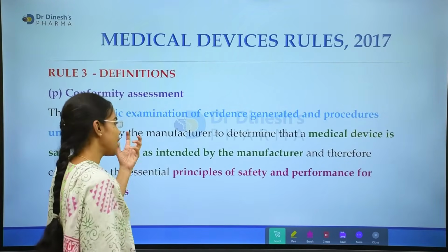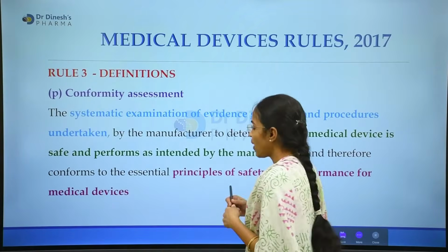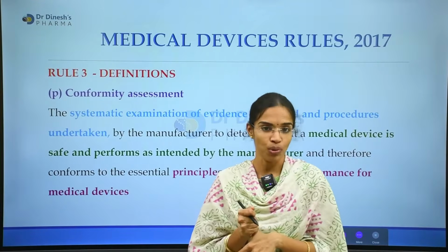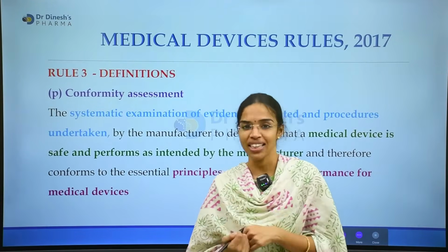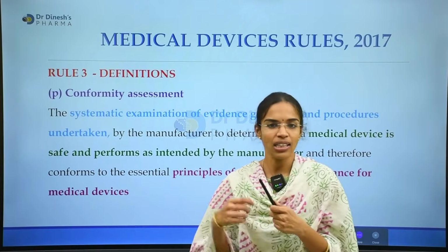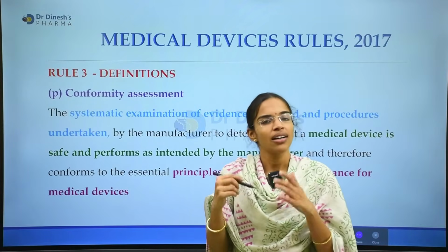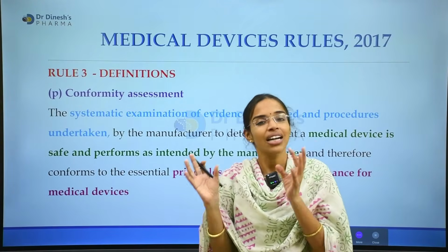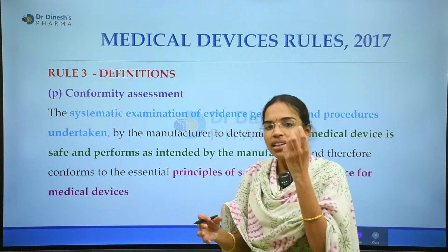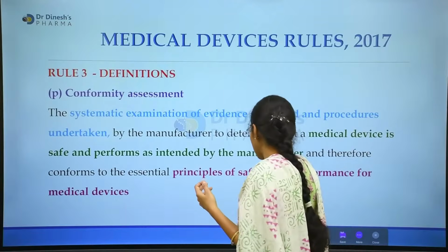It is the systematic examination generated and given by the manufacturer to define that a medical device is safe, along with its performance and safety evaluation report. That is the conformity assessment. It does not depend on whether the device gives a correct or a wrong result. It is not like that. After the complete evaluation protocols, based on the data and information, who is giving that?